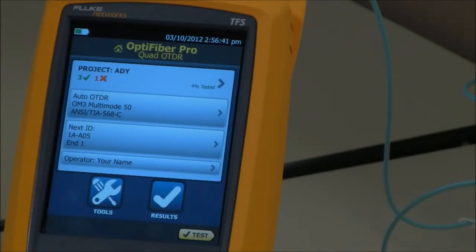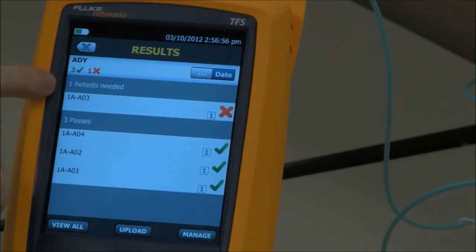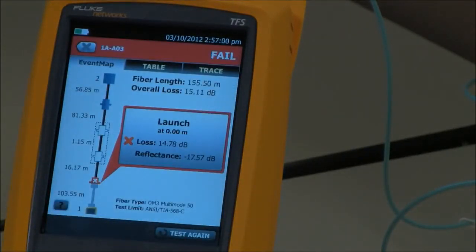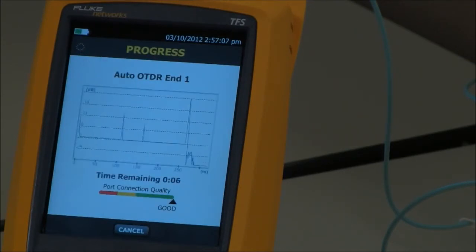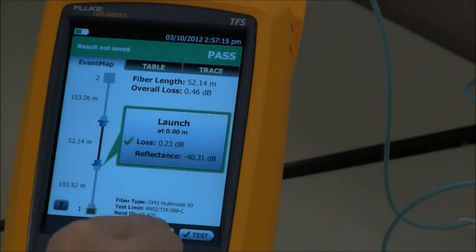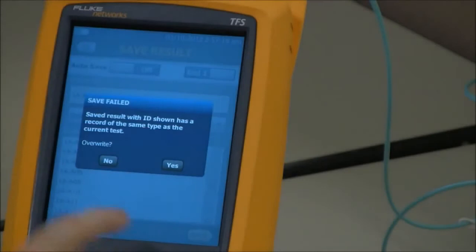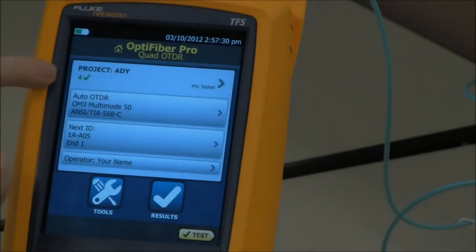This is where the project feature comes in. Instead of downloading all your results to a PC and looking through the LinkWare file to see which one failed, go back to the link that failed, fix it, and then tap Results. You'll see the passing ones and the failing ones that need to be retested. Now that I've fixed it, I'll tap test again. It looks a lot better this time and it passed, so I hit save. It's going to warn me — do I want to overwrite that failing test result? Yes. Now when I go to the home screen, I see only passing test results. And that is the project management feature.